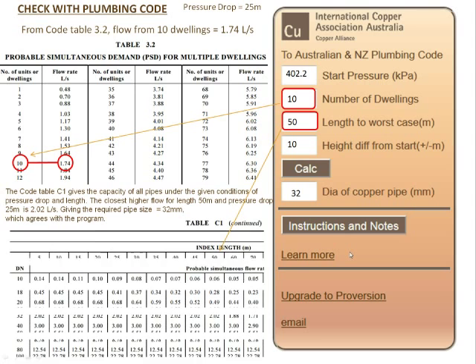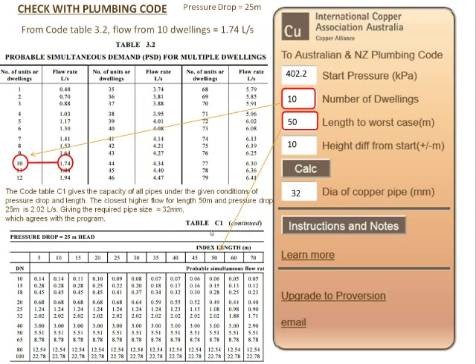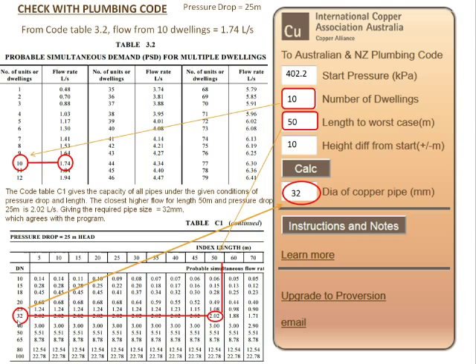Moving on to the next table, which is C1: pressure drop 25 meters, and an index length of 50 meters. At 50 meters we find 2.02, which is the nearest higher flow to our 1.74 from the previous table. So we need this value. Moving across, we get 32 millimeters — which is exactly the answer we got from the calculator.